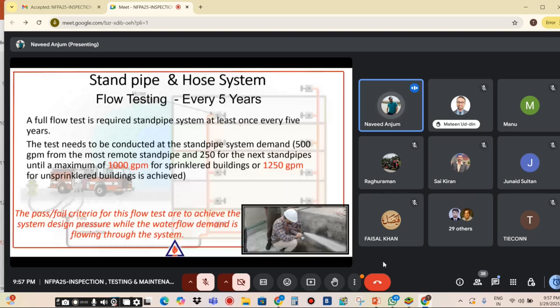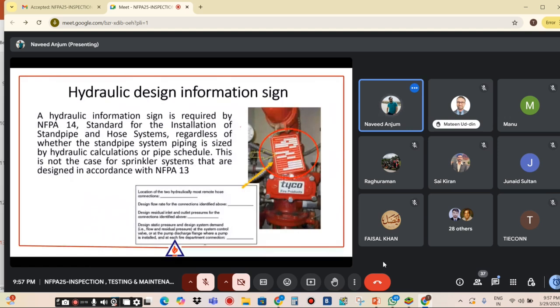Pass-fail criteria for this flow test are to achieve the system design pressure, the pressure at which the system has been designed. If it is meeting that, then it has passed, while the water flow demand is flowing through the system. So due to shortage of time, we will go quickly, and we will discuss more in our question and answers.